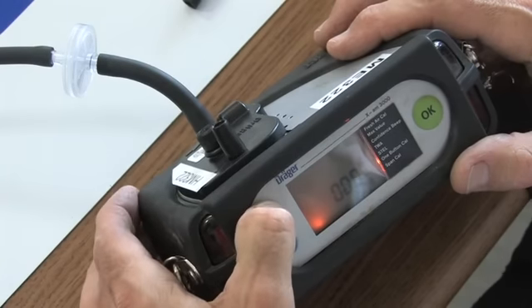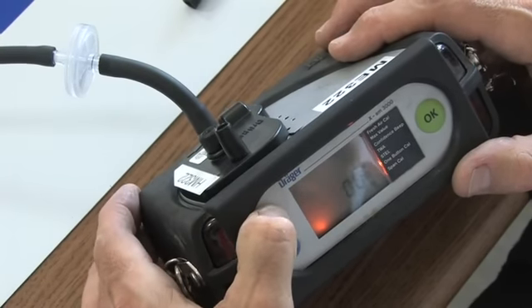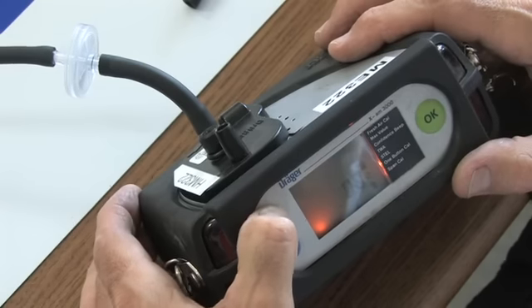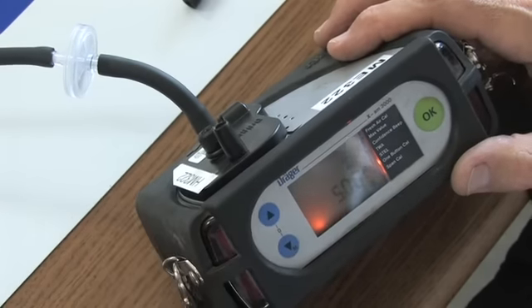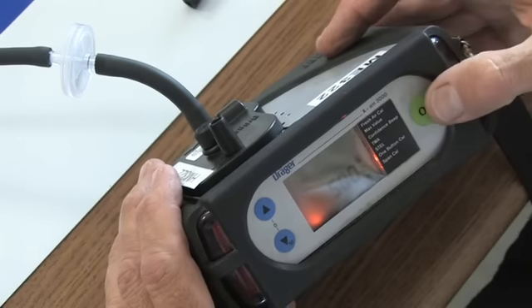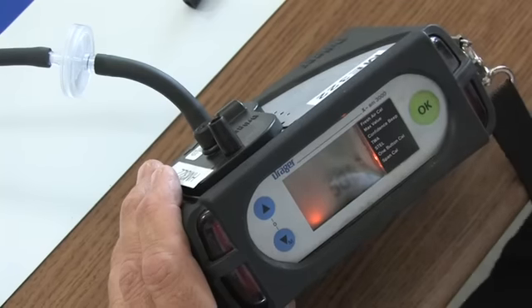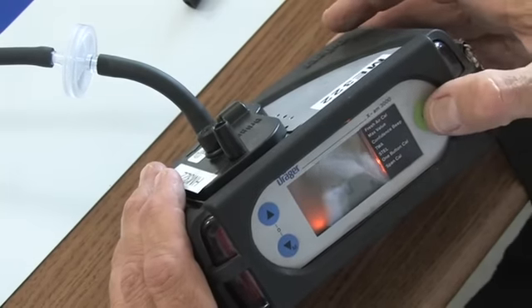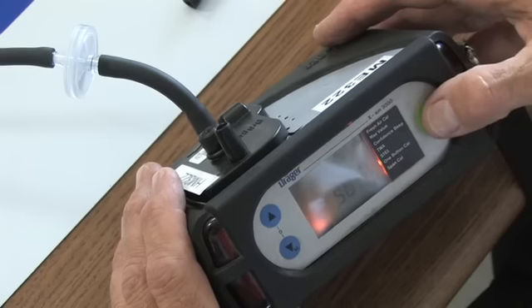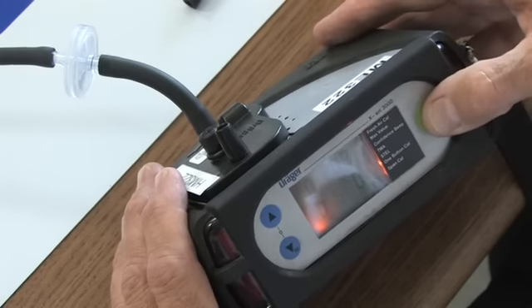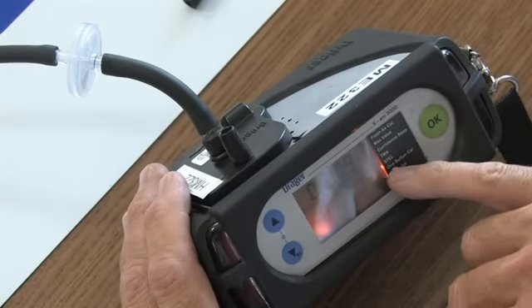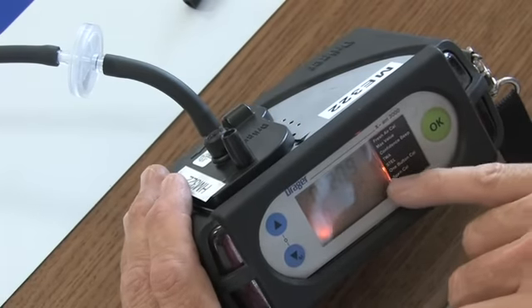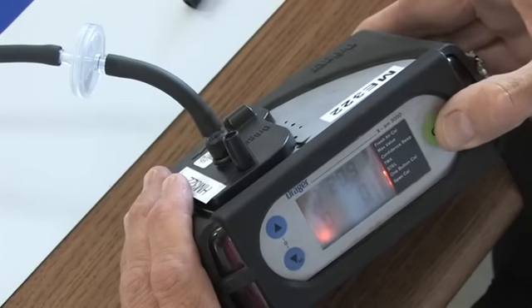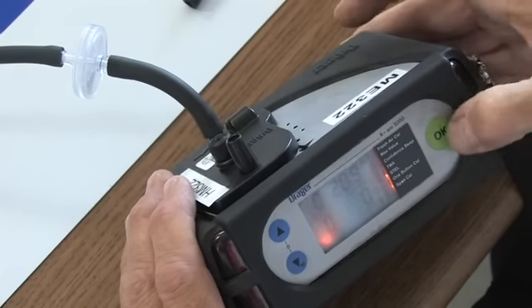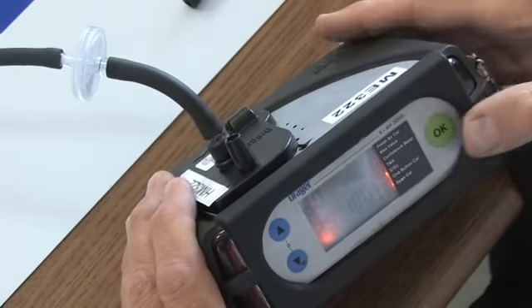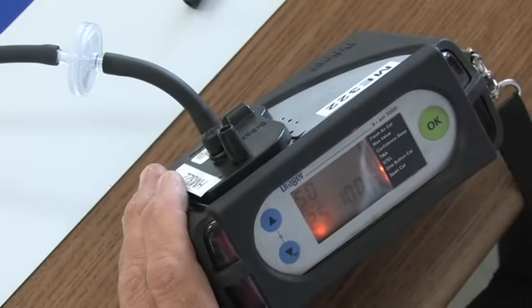So I got to hit the up arrow to keep adding a number. And there's my 5. I hit OK to go to the second digit, OK to get to the third digit. So that kind of operation is somewhat similar to the single gas PAC 7000 in the way it operates. Then I hit it again. And then the arrow is now hitting one button cal on my exterior sticker. I'm going to go ahead and hit OK twice, maybe 3 times. There we go. You saw it took me 3 times to get it to move.